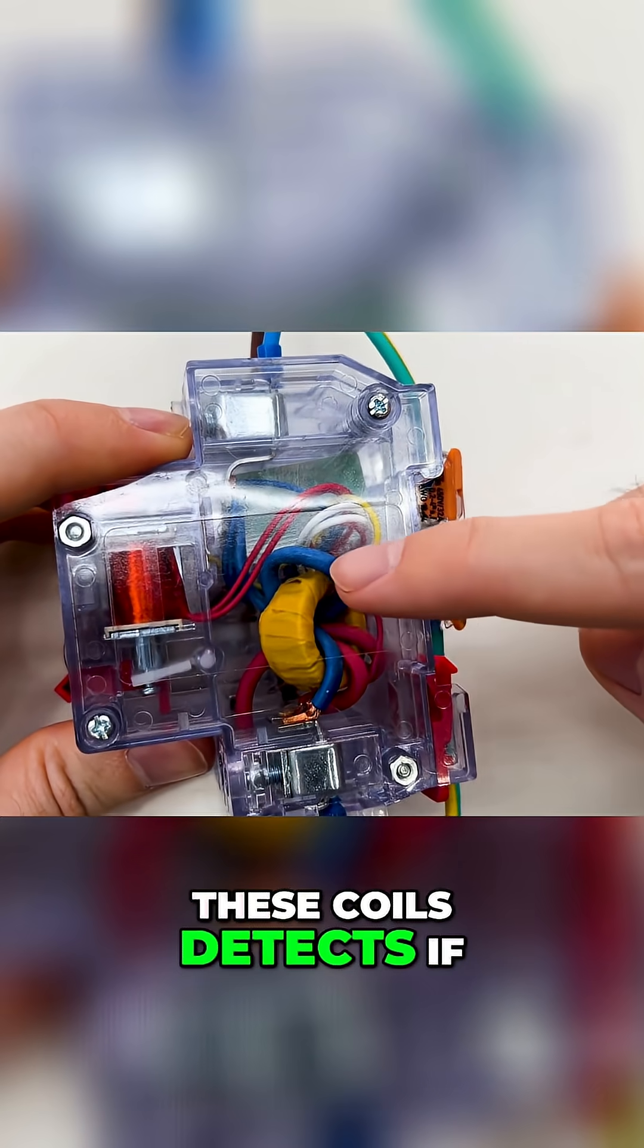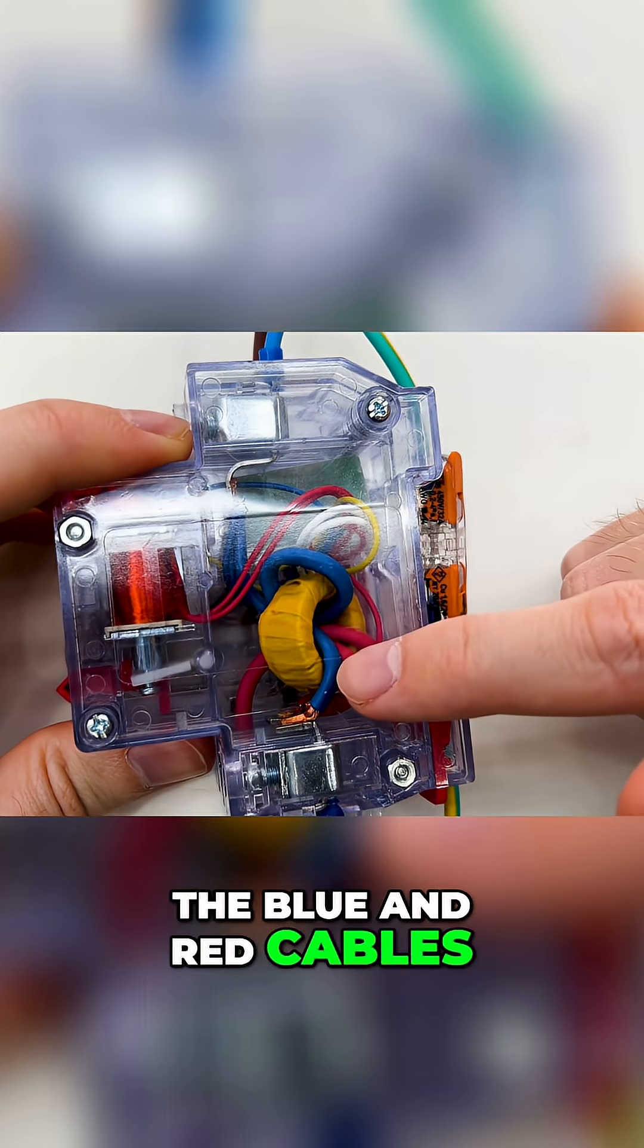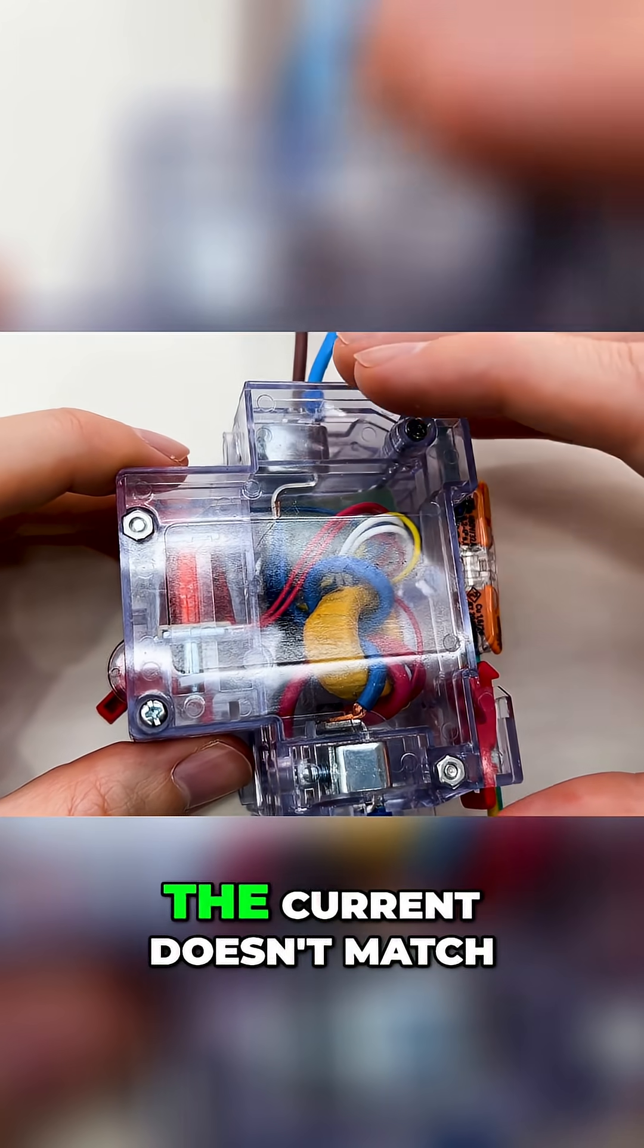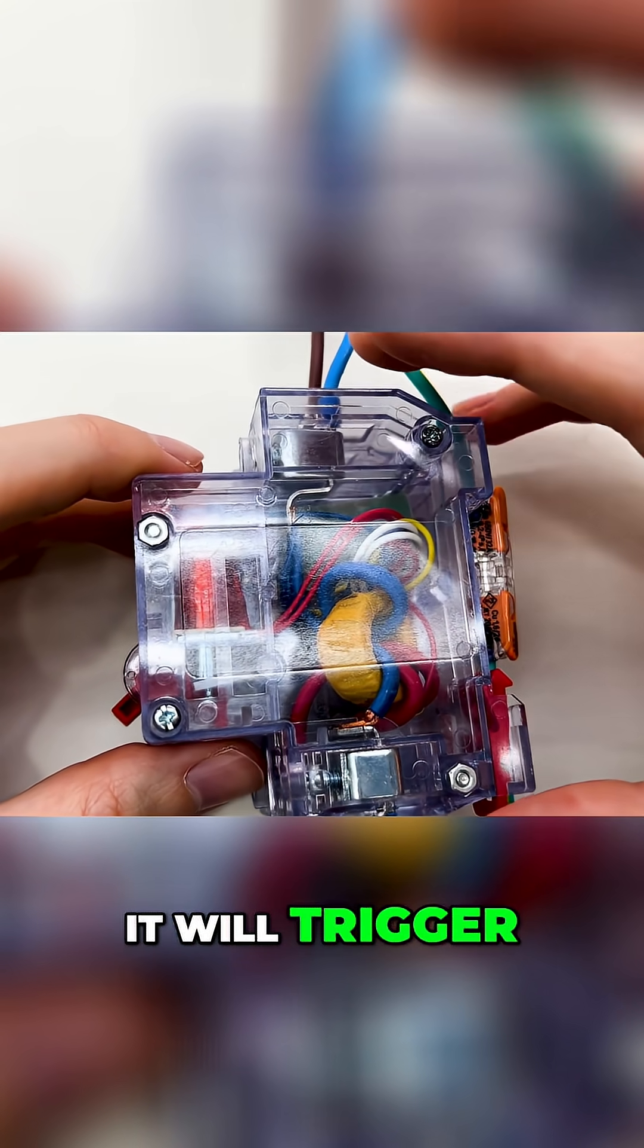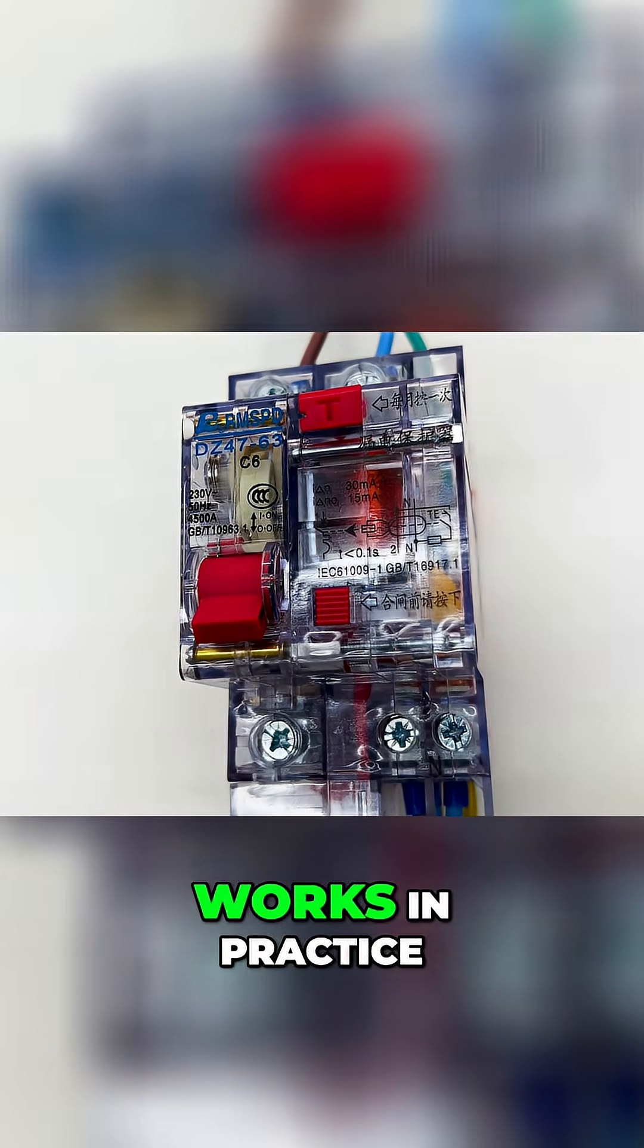These coils detect if the current going through the blue and red cables, the live and neutral cables, is the same. If it detects that the current doesn't match on those two cables, it will trigger. I will show you examples how it works in practice.